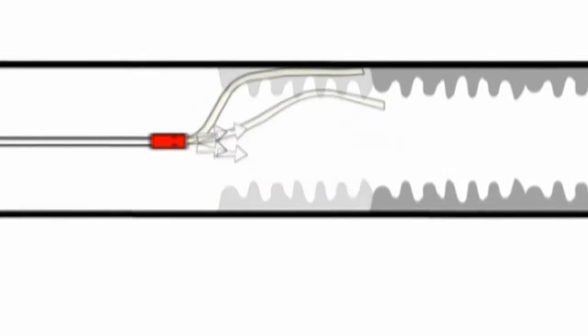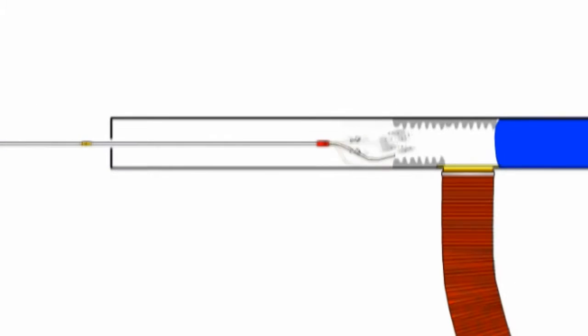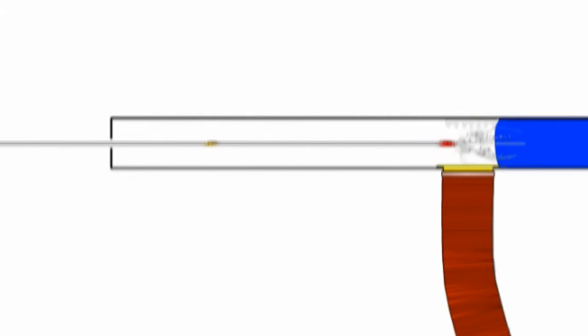Then from the opposite side, you insert a long plastic tube. On the end of it is a rubber whip. The tube is connected to a compressed air tank. When you pull the air trigger, the air makes the rubber piece whip around in the ductwork. It bangs into the sides and dislodges the dirt, which is then sucked out the other end of the vent into the machine outside. Right by where the rubber whip attaches to the plastic extension tube, there's also an air nozzle that blows air in the same direction that the vacuum is running. This is the most effective way of cleaning ductwork.